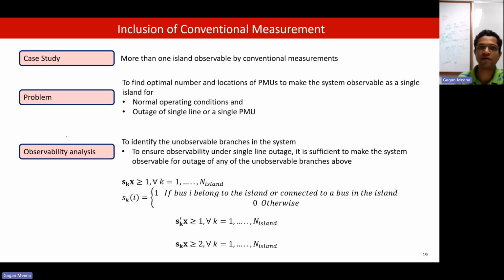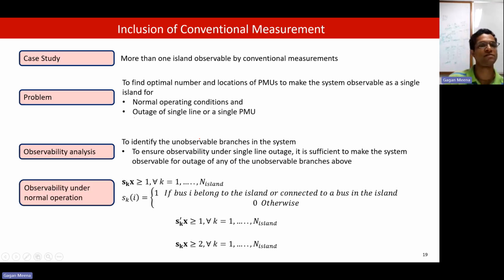We have already discussed how to handle outage of a single PMU and outage of a single line. The only additional thing here is that there are a number of observable islands, and we want to make them a single observable island, so the PMUs have to be placed such that we identify the unobservable branches. To ensure observability under single line outage, it is sufficient to make sure the system is observable for outage of any of the unobservable branches. So under normal operation we have S_k into x greater than or equal to 1.